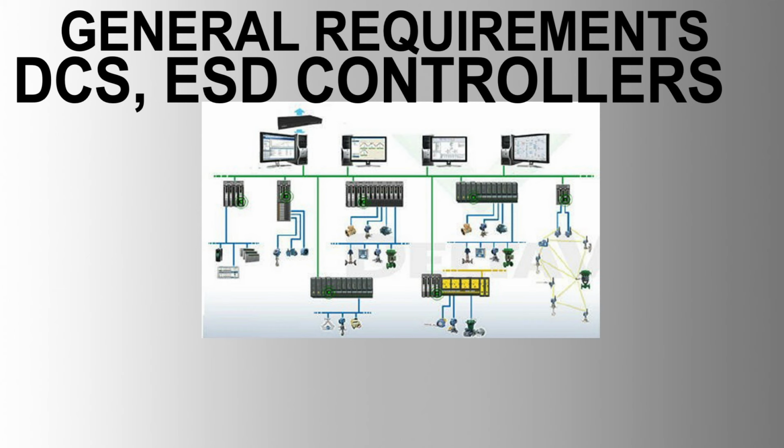11. ESD logic. Modular structure. The ESD logic shall be based on a modular structure comprising a number of discrete subsystems, each one defining the shutdown logic of a discrete section of the process. Logic functions are executed in the ESD system, often using triple modular redundant TMR systems for critical applications.